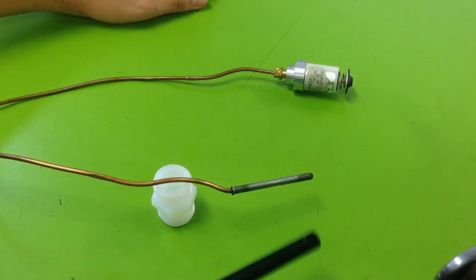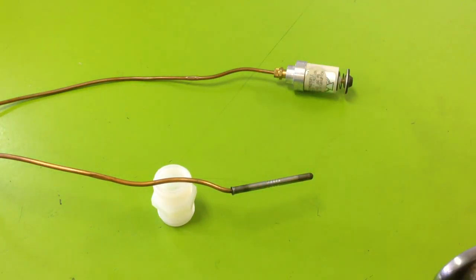And you can see I pressed it. The valve stayed depressed. That means I have a working thermocoupler.